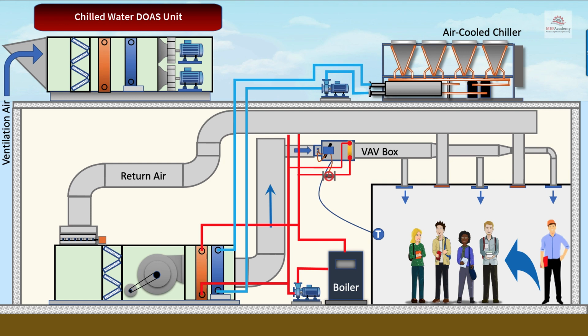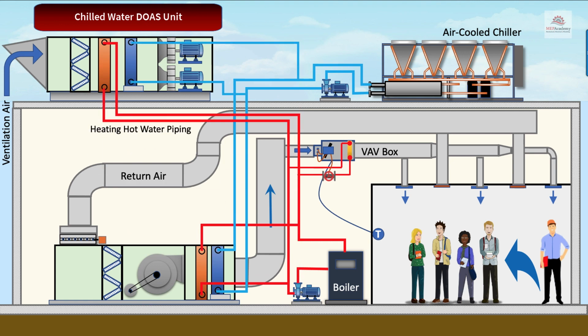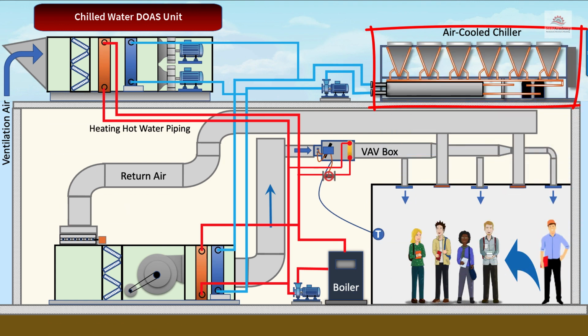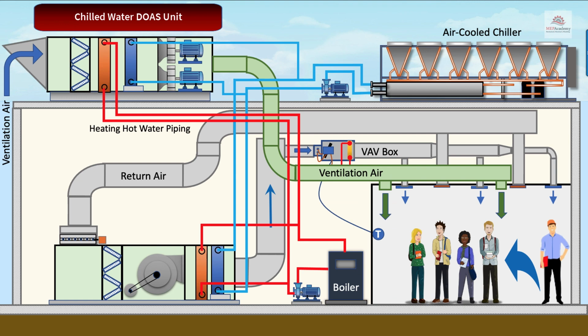This will require the connection of heating hot water piping to the unit as well as chilled water piping. Since all the load for the ventilation air is being served by the chilled water, the chiller needs to be upsized. A larger chiller is put on the roof to feed the load of the DOAS unit and the air handling unit. Sheet metal ductwork is used to feed the space directly.